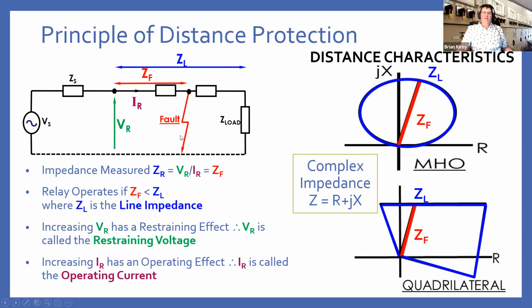However, if your impedance drops below that, so your fault impedance becomes less than your line impedance, then you're inside this circle here. Or alternatively, you may have what's called a quadrilateral characteristic. These are used in parts of Europe, like France, Germany, and associated countries that use similar schemes to them. So we can say that we have two key elements to our distance protection.